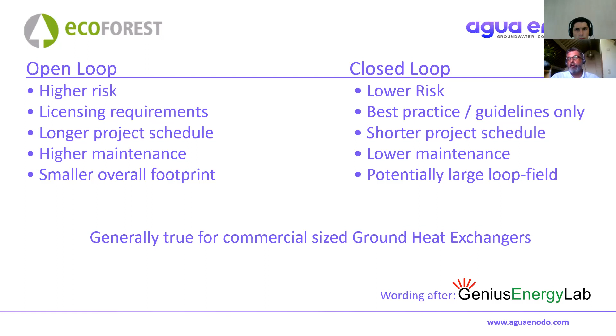Maintenance: with an open loop system, we're obviously interacting with the environment in a closer way. We're abstracting raw groundwater out of the ground - not treated groundwater, raw groundwater - and dealing with that at the surface in our plant. There are heat pumps that, with certain water quality parameters, can have the water go through directly, but often we'll have a plate heat exchanger that separates the plant and the heat pump from the ground.